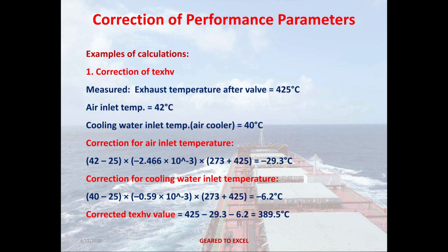So now the corrected exhaust temperature after the valve will become 425 minus 29.3 minus 6.2, and this is the value. Corrected temperature after the exhaust valve is 389.5 degrees Celsius.